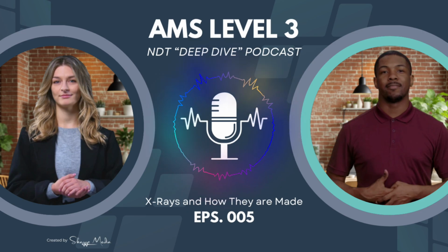What's the benefit? Big benefits. Enhanced high-energy output, much shorter exposure times, maybe 30% less, and often longer tube life because the heating is more consistent. But remember, the X-rays produced via Bremsstrahlung are still a spectrum, not monoenergetic, because the deceleration process itself is random. Okay, that's clear. And how the circuit is grounded matters too.